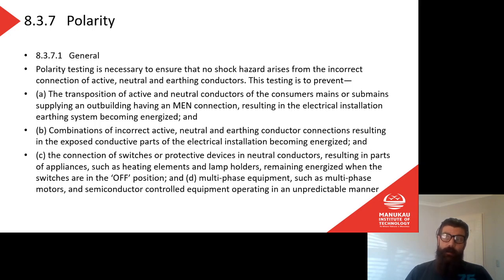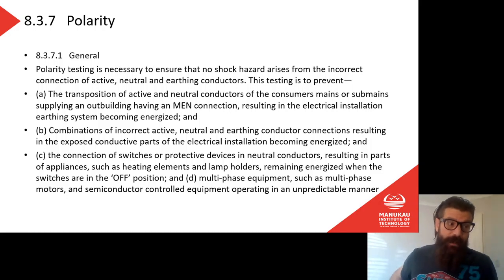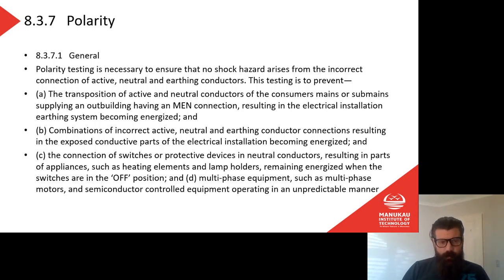If you see the line mechanics, when they do connections at the pole, they will actually stab a post into the ground with a wire running off it, and then they can test between that wire and each of the conductors to tell which one is which. But it still happens from time to time. Line mechanics get lazy and they don't do that test. They just look, oh, yeah, that must be the live, that one must be the neutral, and every now and then you'll hear about an incorrect connection where the mains is coming into the building. We usually don't do that connection. An electrical inspector would do that connection, so they would generally be responsible to test whether the active and neutral conductors are coming to the right place. But we can also do that test.